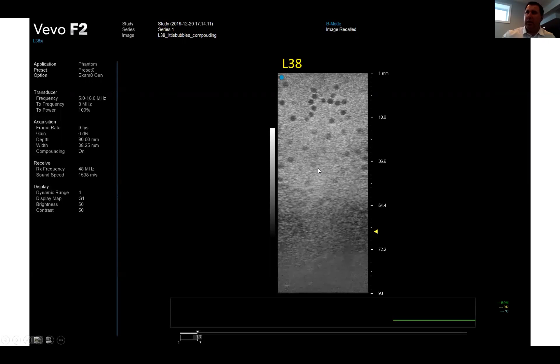I just wanted to give you a sense of how the images actually look on the system. This is a somewhat older image that we had done throughout the development phase, but I think it serves the point here, which is to show you, this is what we call a high frequency phantom that has a variety of small voids or almost cyst-like voids that are built into the phantom. You can see these tiny little dots if I just use my cursor here. So these are little voids. This is done with the L38. So again, we're in the frequency range. We're running around 8 megahertz. It's got a bandwidth from about 5 to 10 megahertz. And you can see that we can start to detect some of these small voids. But as we get deeper and more out of the elevation focus, the beam of this transducer is quite wide, and the resolution not being as high, we start to lose the ability to detect those small anechoic spheres.